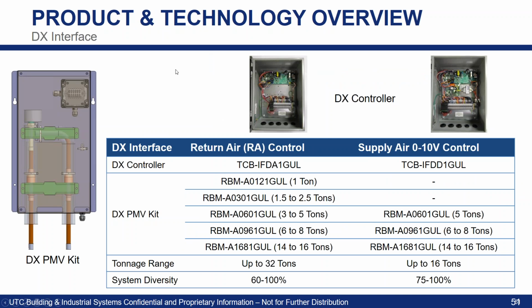So the DX interface, this is something that's coming to light more and more. This is what I consider the non-traditional application of VRF, and traditional being all the fan coils that VRF has to offer. Non-traditional being when you're using a cluster of VRF condensing units to serve an evaporator coil and, let's say, a central station air handling unit, and you want to utilize VRF technology for an indoor air handler up to 32 tons or up to 16 tons.